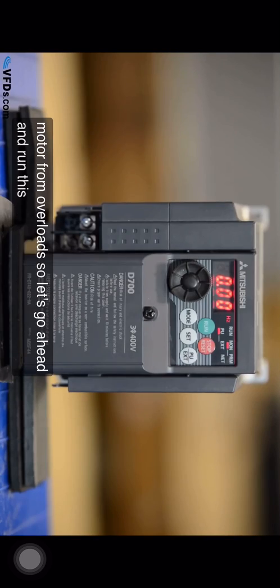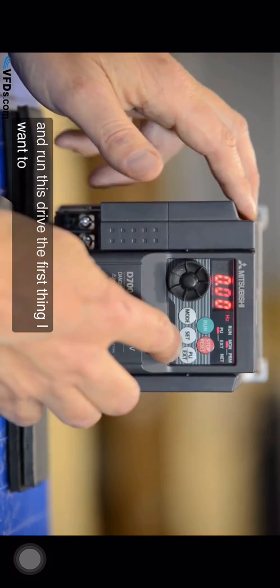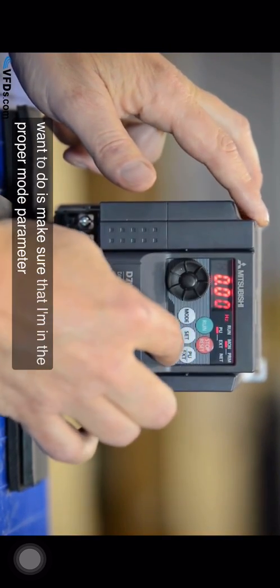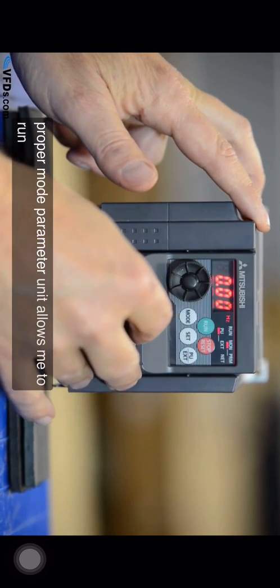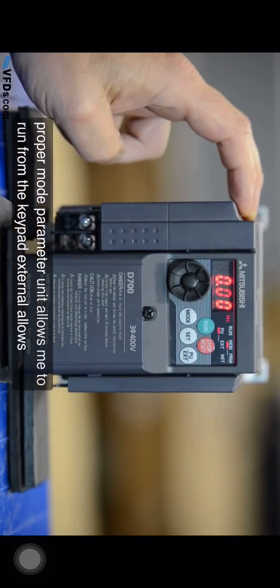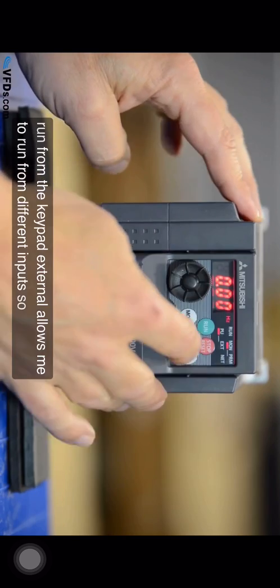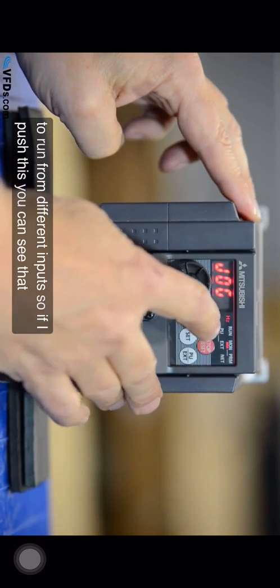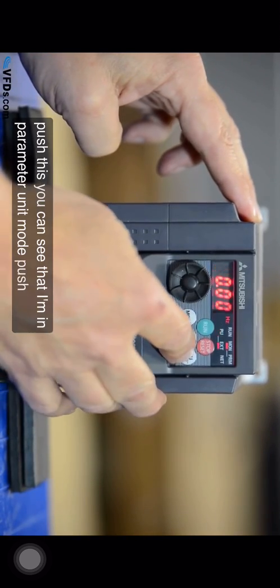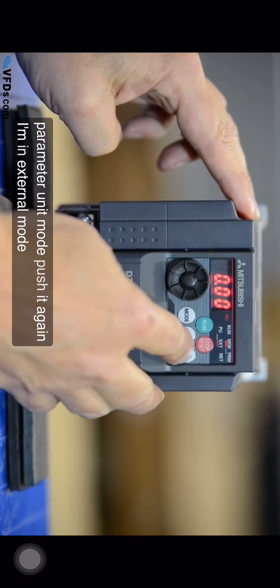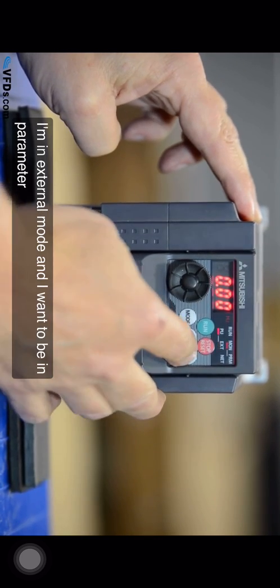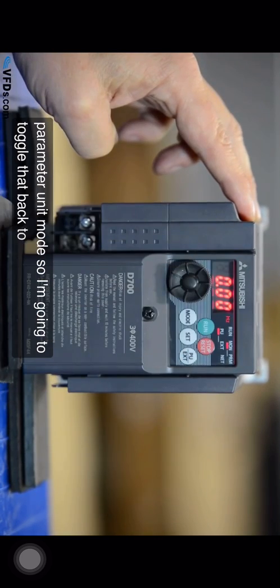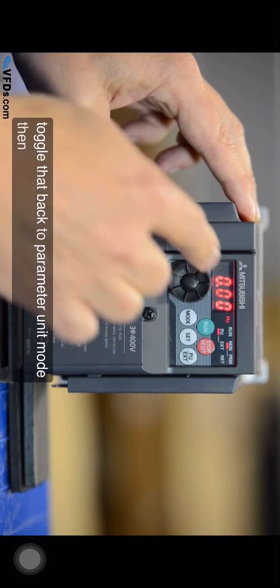So let's go ahead and run this drive. The first thing I want to do is make sure that I'm in the proper mode. Parameter unit allows me to run from the keypad. External allows me to run from different inputs. So if I push this you can see that I'm in parameter unit mode. Push it again, I'm in external mode and I want to be in parameter unit mode so I'm going to toggle that back to parameter unit mode.